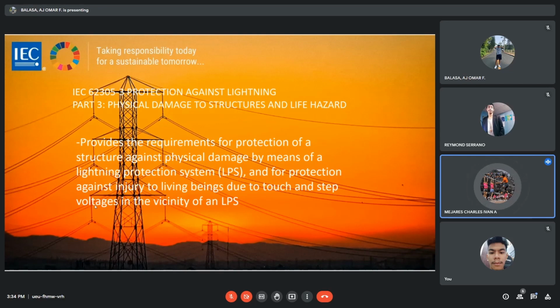IEC 62305-3, Part 3: Physical damage to structures and life hazard. It provides the requirements for protection of a structure against physical damage by means of a lightning protection system, or LPS, and for protection against injury to living beings due to step and touch voltages in the vicinity of an LPS. This standard is applicable to the design, installation, inspection and maintenance of an LPS for structures without limitations of their height. Second, it establishes measures for protection against injury to living beings due to touch and step voltages.